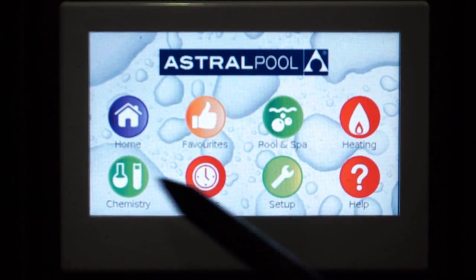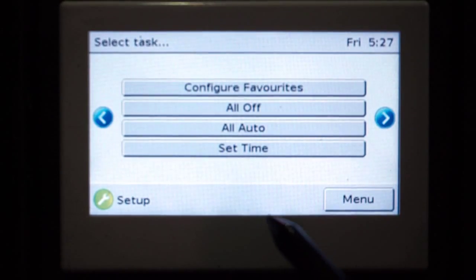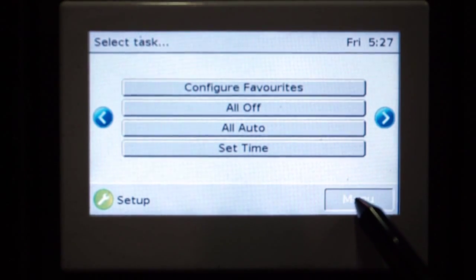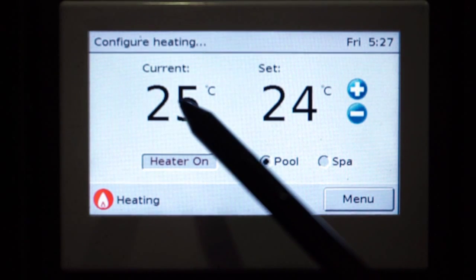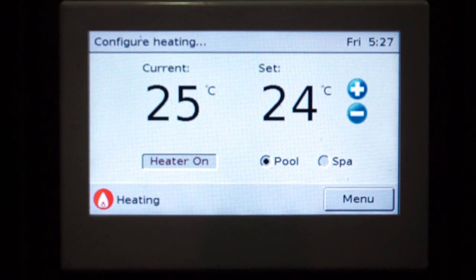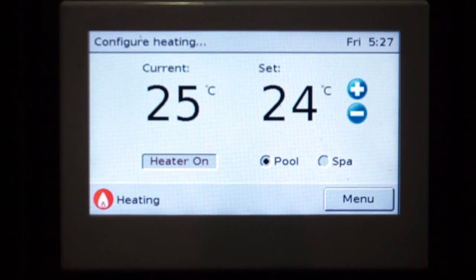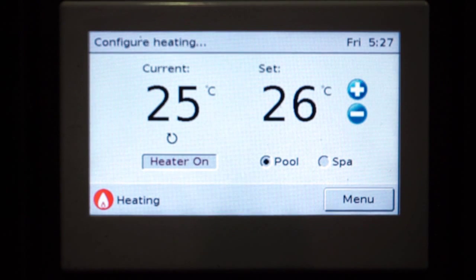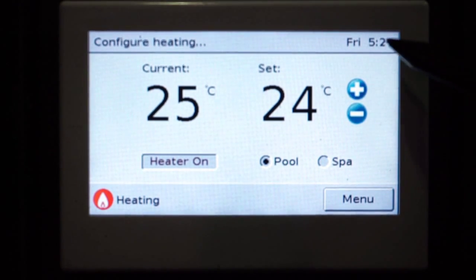Now what we're going to do is simply press home, all off, all auto as per normal. Our timer is 5:27 so we should be in a timer cycle. What we need to do is press our heater on. Now what will happen is even though we are currently at 25 degrees and our set point is only 24, it will start and cycle the filtration pump as well as the heater pump if it needs to, for 2 minutes, and then it will again cycle at the top of every hour. So as you can see the heater is not actually on at the moment. If we press our temperature and raise our temperature it will now turn the heater on. But at the moment it is just running our filtration pump, which it will cycle for 2 minutes and then at the top of every hour afterwards.